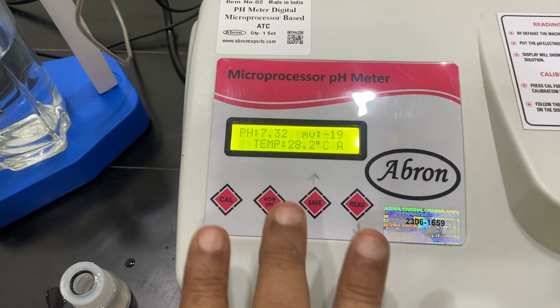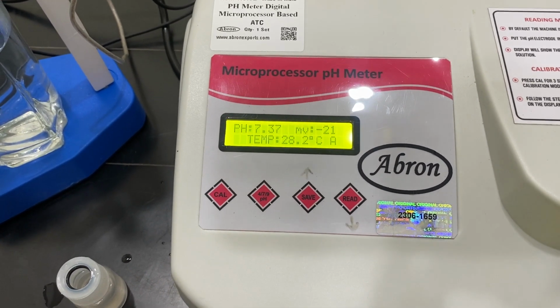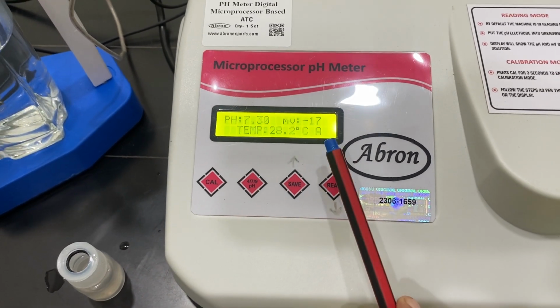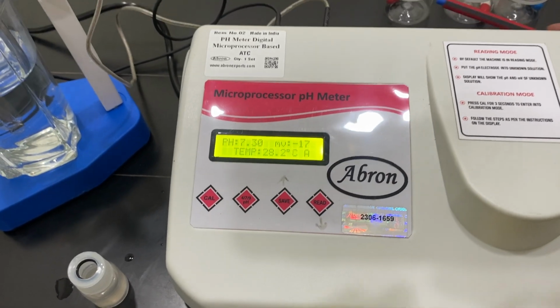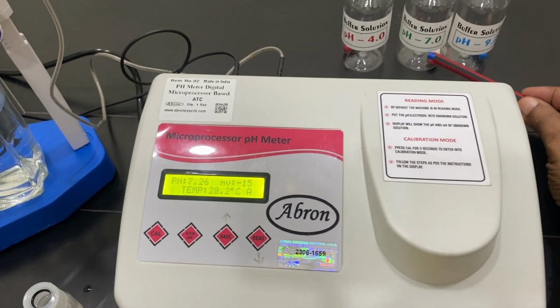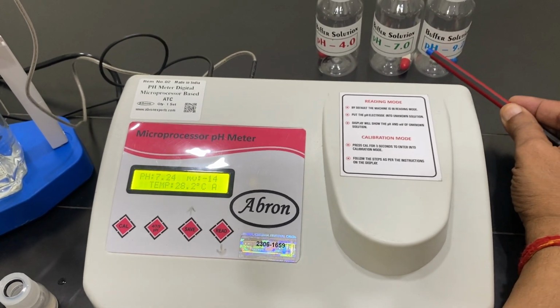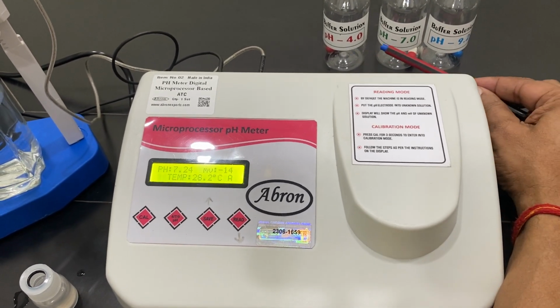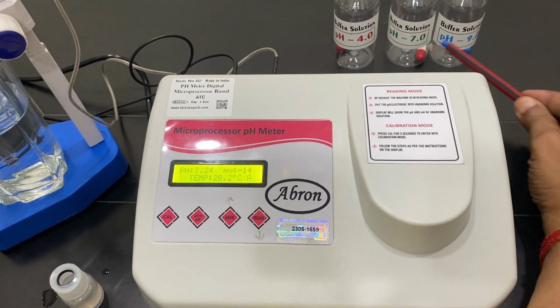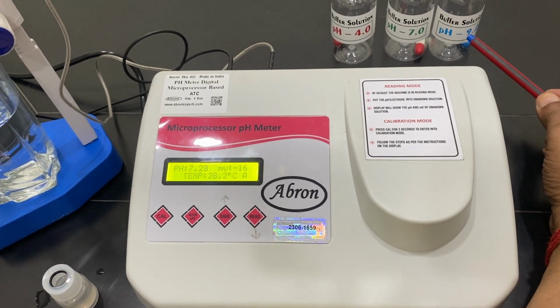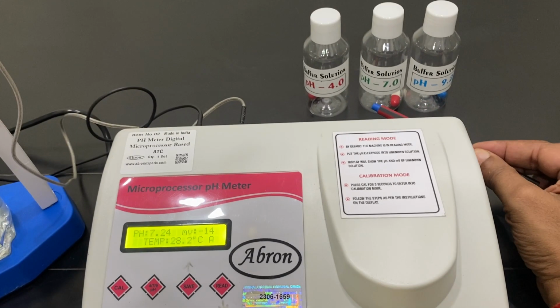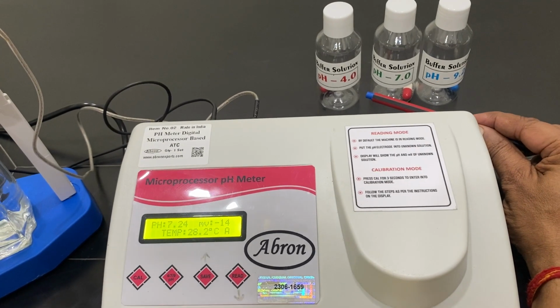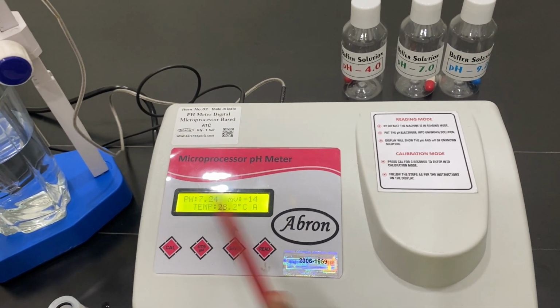For how to calibrate the temperature probe, the pH and the instrument, please see the other video. This instrument has 3 modes. In 2 mode, pH 4 and 7 can be calibrated, or 7 and 9. 2 mode is 4 and 7. 3 mode is 4, 7 and 9 pH calibration. And then there is another mode, 5 mode calibration, which will be visible here.